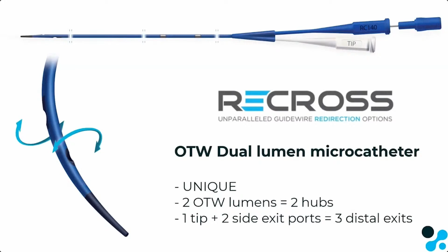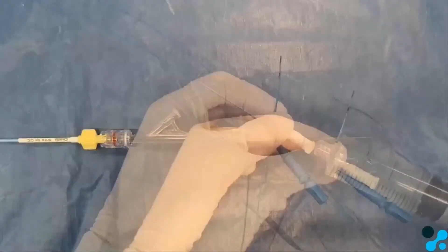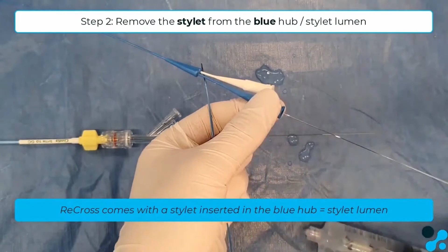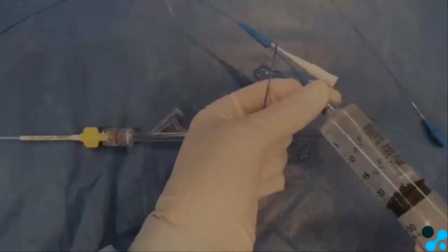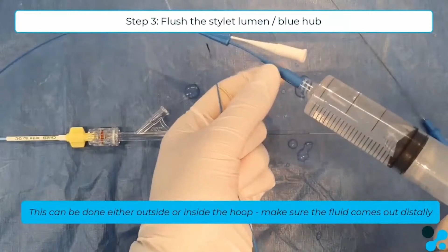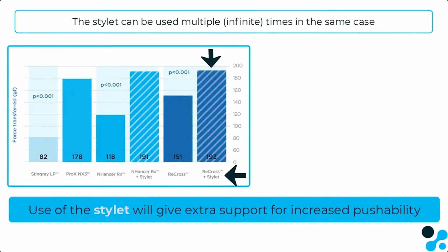In this instruction video, we will show you how to use the unique Recross over-the-wire dual lumen microcatheter with 3 distal exits. The device can be taken out of the hoop and should be flushed in both of the over-the-wire lumens. This can be done either inside or outside the hoop. The blue hub comes with the stylet inserted. Take it out and flush that lumen as well. Bring it back in and use it during insertion of the Recross device. The stylet gives higher pushability during insertion and advancement of the device.